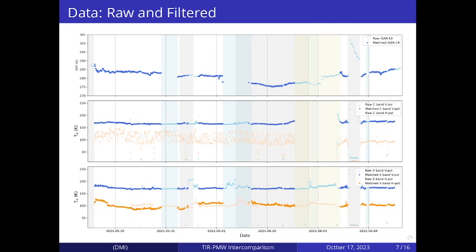The ISARs are designed to close off the mechanism in case of rain when it is detected to protect the instrument. So whenever there was rain, there are gaps of the infrared data.